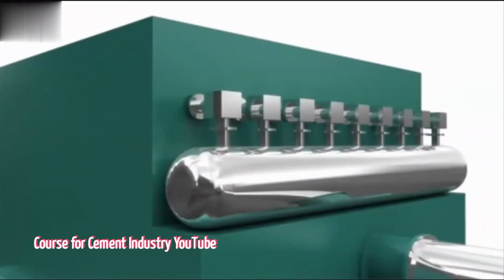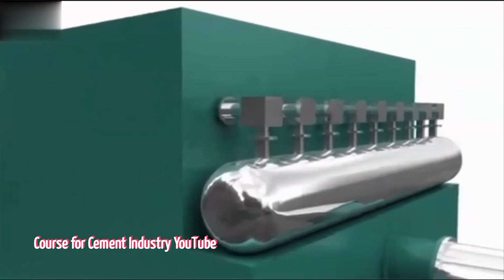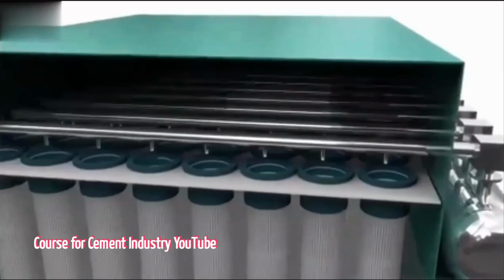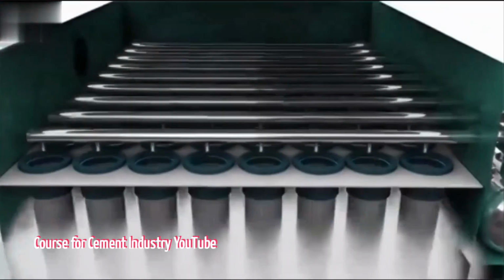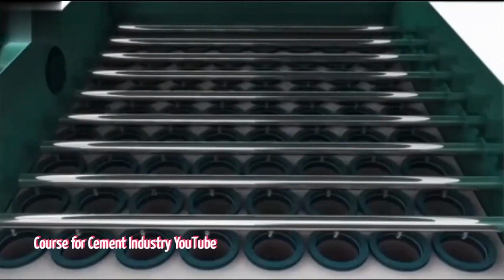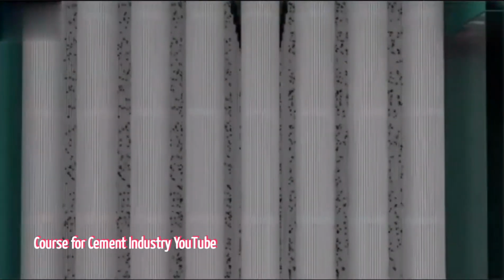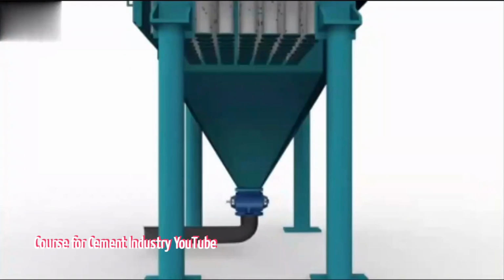Maybe. But here's the fascinating thing. Initially, this dust cake actually helps the filtration process. Really? How does that work? You'd think more dirt would be worse. Well, think about it. A brand new filter bag has pores defined by the fabric weave. But once that initial layer of fine dust builds up, it creates a much finer, more intricate filtration layer on top of the fabric. I see. The dust itself becomes the filter medium. Exactly. And this dust cake is often much more efficient at trapping those really fine particles than the original bag fabric was on its own. So the dirt is filtering the dirt.